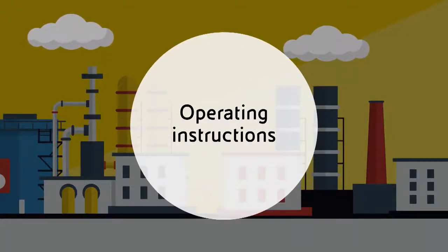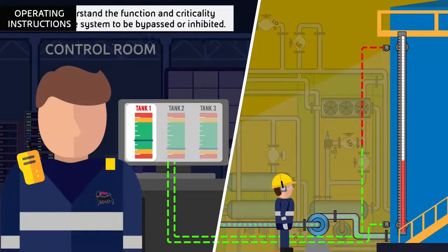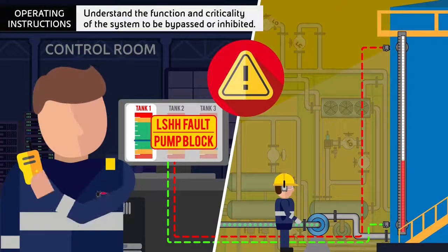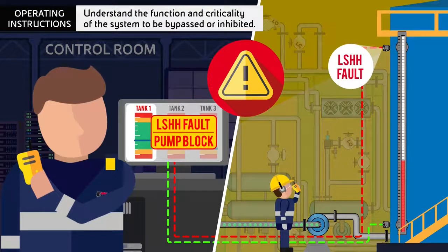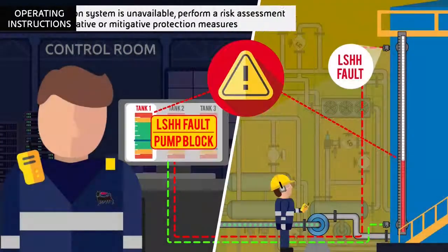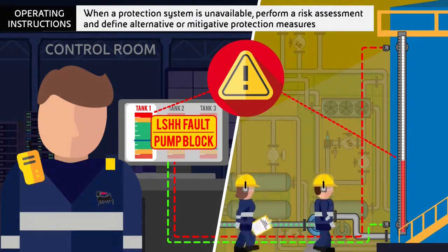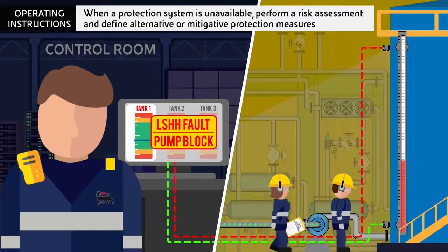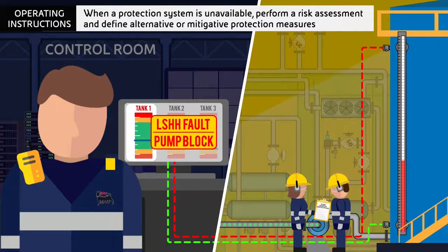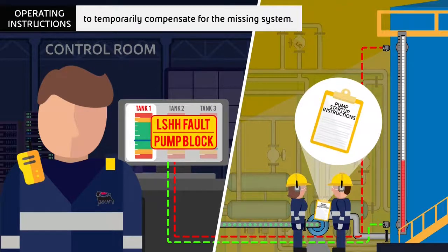Operating instructions. Understand the function and criticality of the system to be bypassed or inhibited. When a protection system is unavailable, perform a risk assessment and define alternative or mitigative protection measures to temporarily compensate for the missing system.